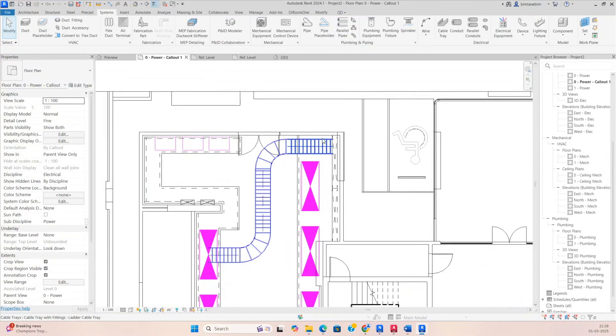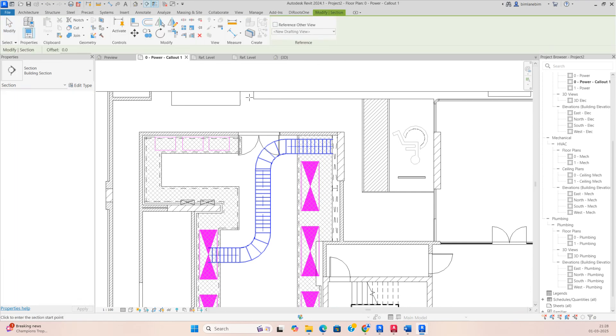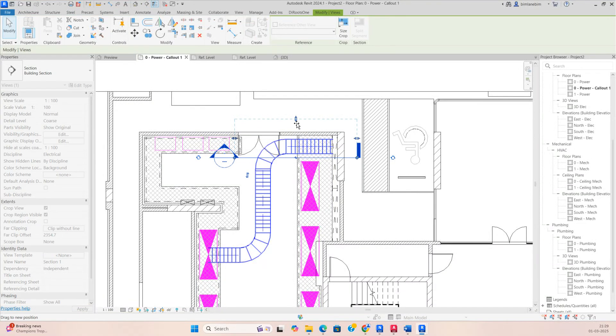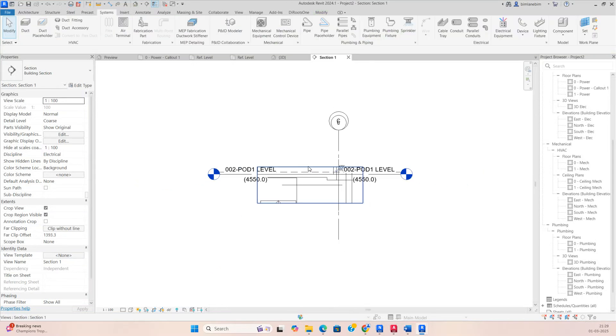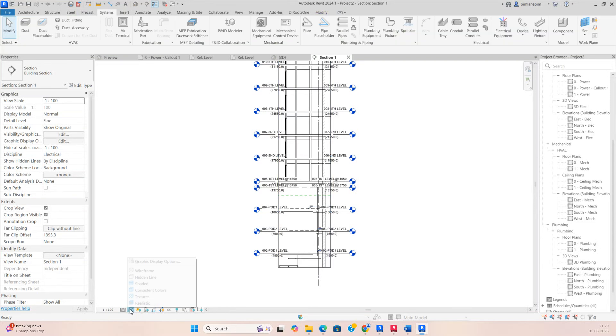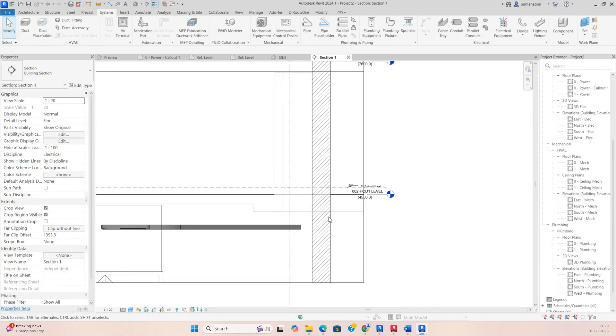There is another riser where all cable trays need to go through. Create a section here, go to View, stretch the crop region, then set it to Fine and Shaded. Change the scale so you can see the cable ladders clearly. From here I need to use channel cable tray and run it up to where required.